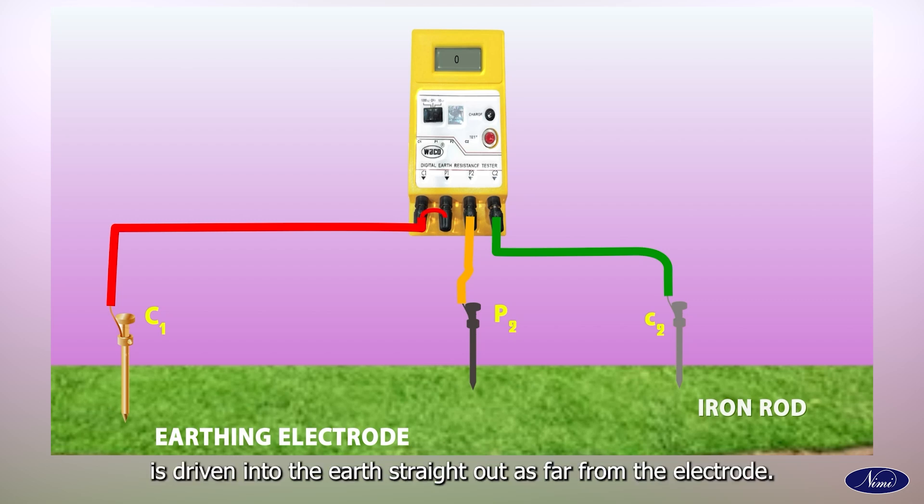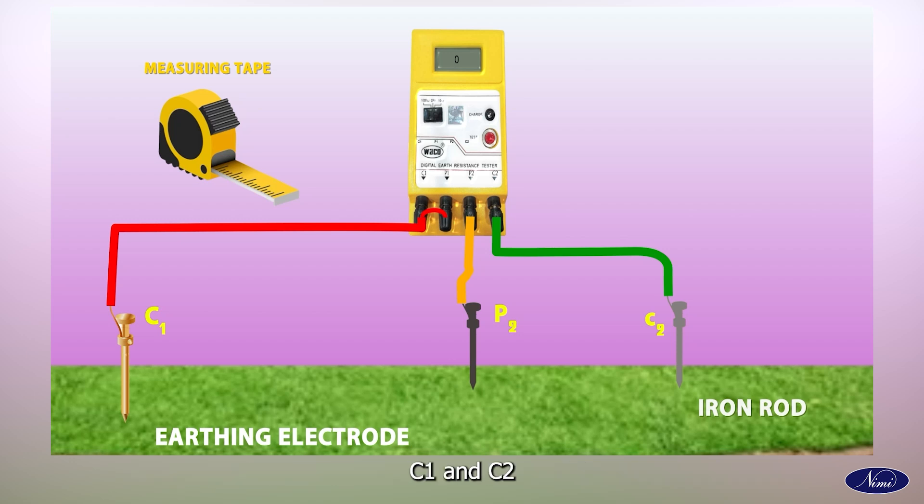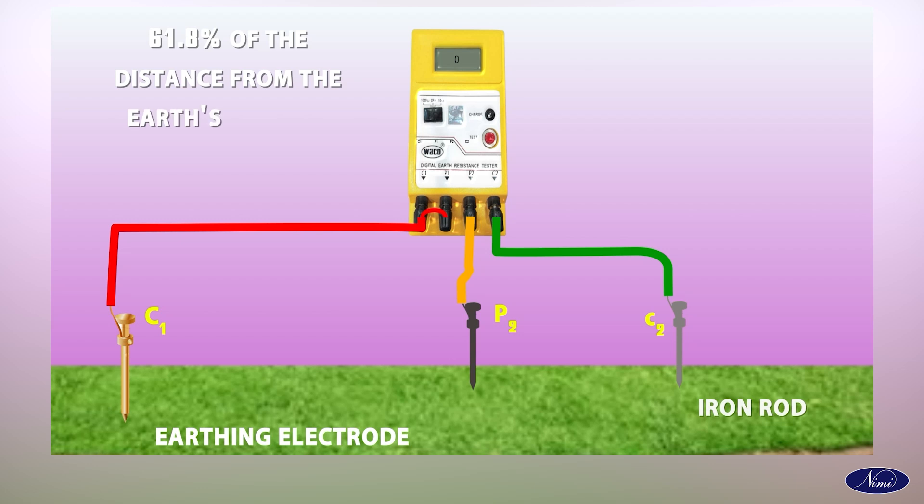Now the C2 reference rod is driven into the earth straight out as far from the electrode C1 under test as possible. Potential reference P2 is then driven into the earth at a set number of points roughly on a straight line between C1 and C2. Use a measuring tape to determine the distance between points C1 and C2. Place the potential electrode P2 61.8% of the distance from the earth's current electrode C1.